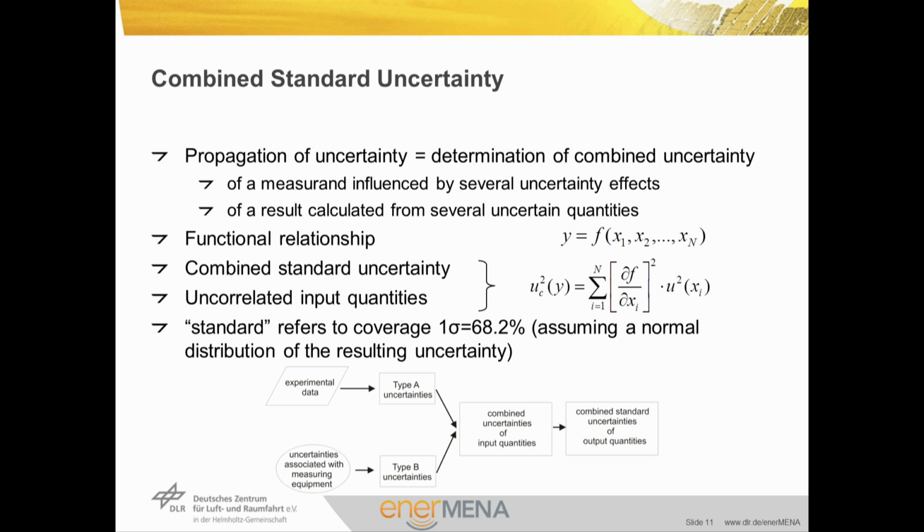Essentially, this is achieved by adding up the product of the squared sensitivity and the square of the standard uncertainty for all effects or contributing measurements, as expressed by the formula on the right. It adds up all uncertainties of contributing quantities weighted according to how the measurement result varies with changes in these quantities. This slightly simplified formula is only valid for uncorrelated input quantities. Should there be a considerable correlation between input parameters, further terms need to be included.